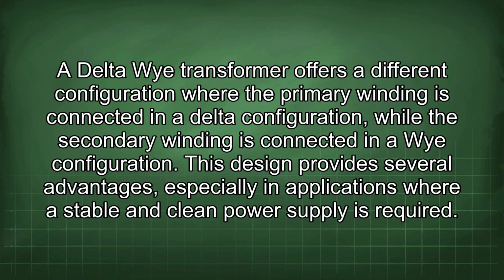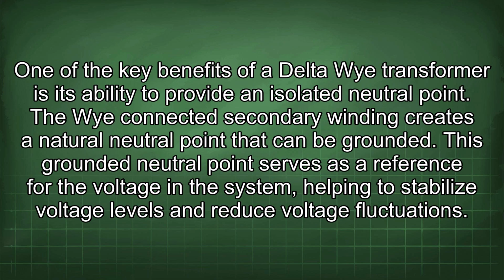A Delta Wye transformer offers a different configuration where the primary winding is connected in a Delta configuration, while the secondary winding is connected in a Wye configuration. This design provides several advantages, especially in applications where a stable and clean power supply is required. One of the key benefits of a Delta Wye transformer is its ability to provide an isolated neutral point.